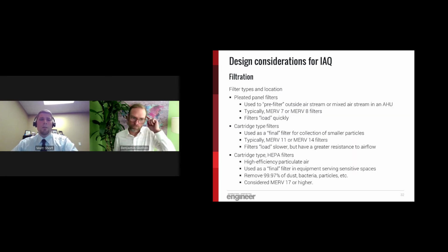In air handling equipment, the following filter types are most common. Starting out with pleated panel filters, these are typically used as a pre-filter to capture some of the larger particles that we see in the outside airstream. We most often see these specified as a MERV 7 or MERV 8 filter rating, although we have seen that increasing lately. These filters do load quickly as they're capturing the larger particles in the untreated airstream and will need to be replaced more often by the facility owner.